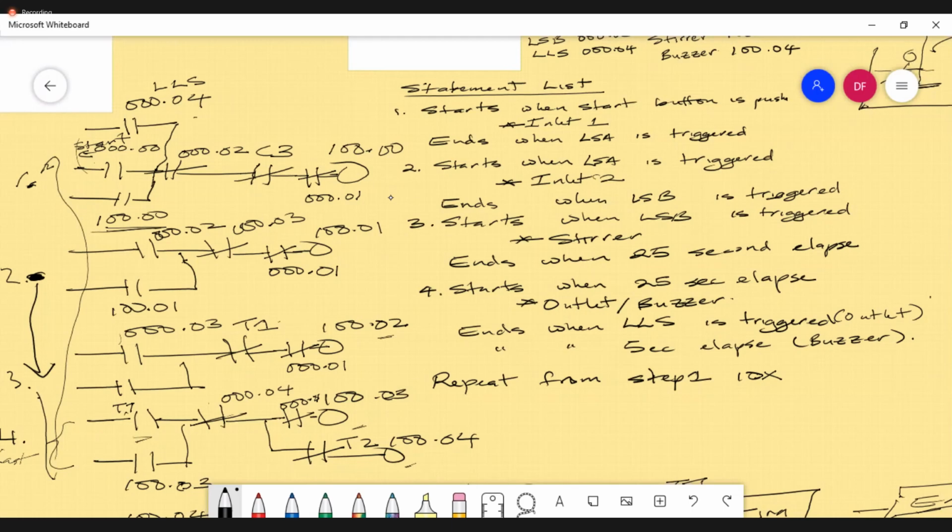Because most automation systems have that, it is the get out of jail card. But let me say most panels come with a separate start and a separate stop. You don't have the single pole single throw switch that you're going to use as one mean start and one mean stop.